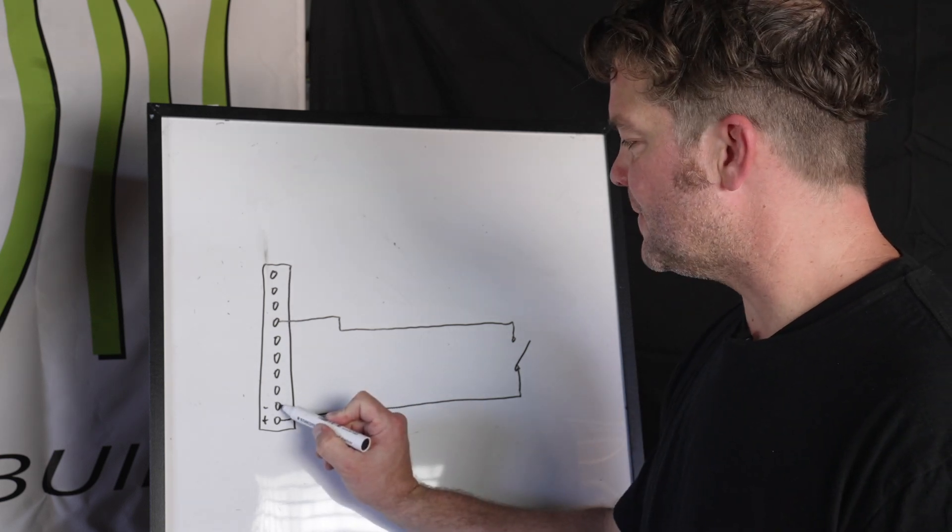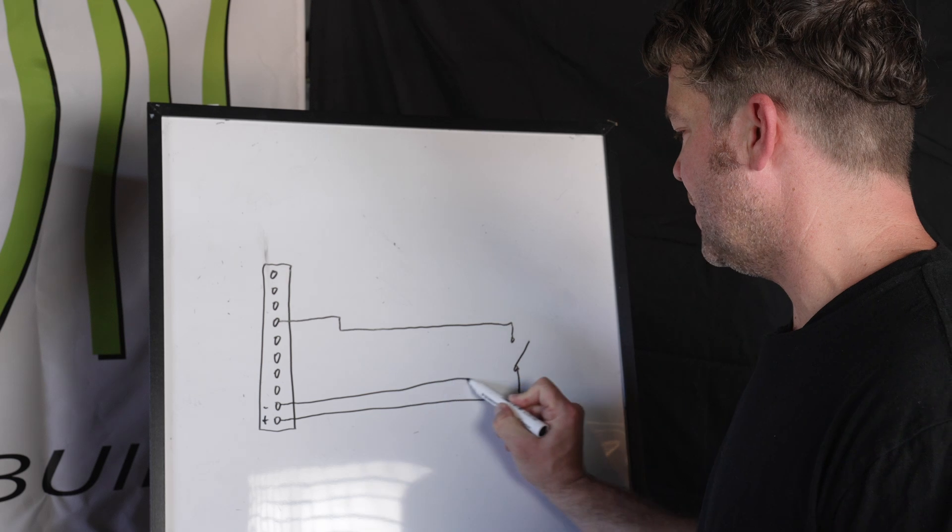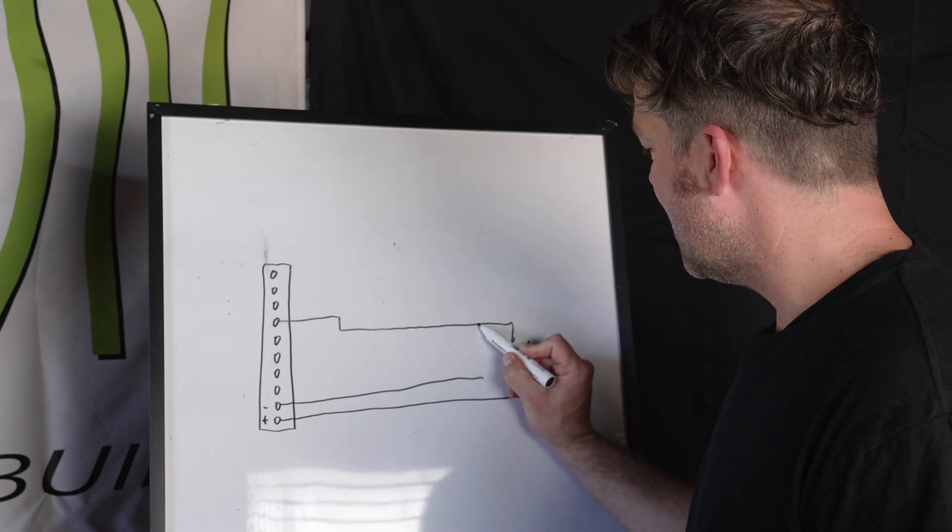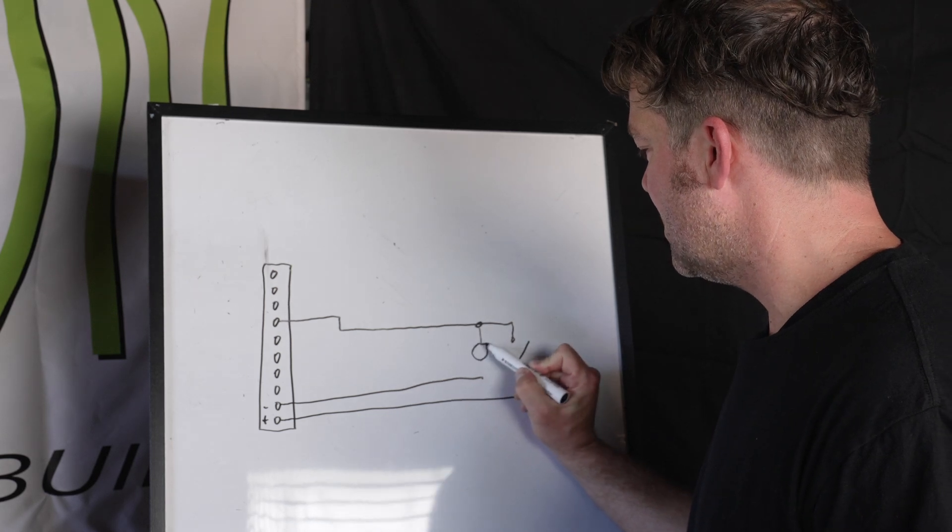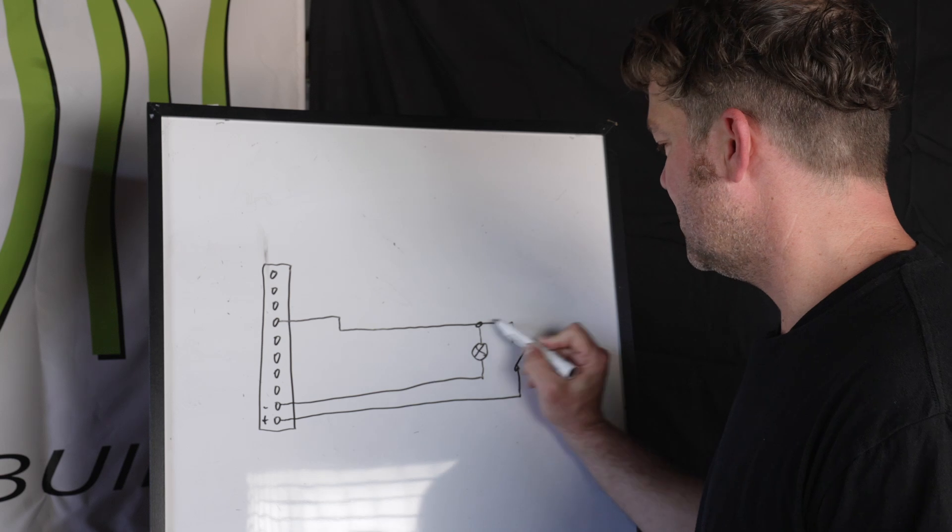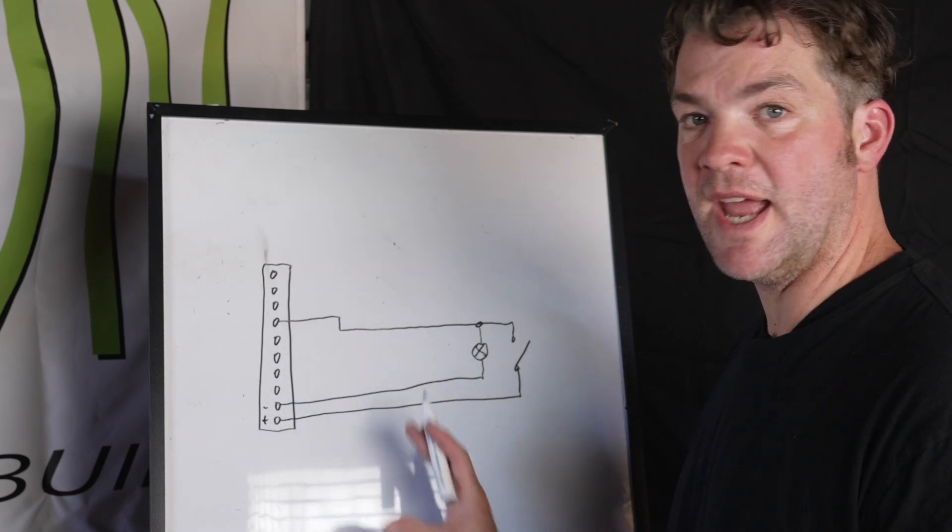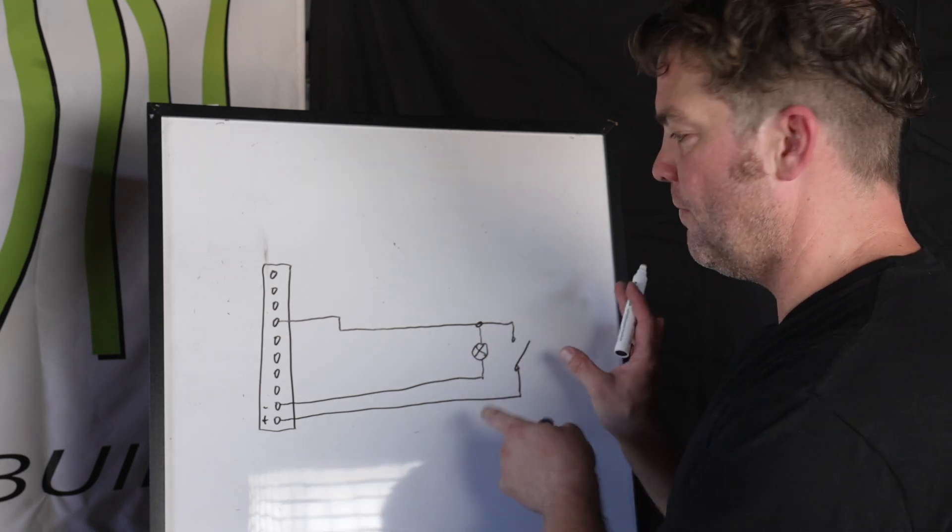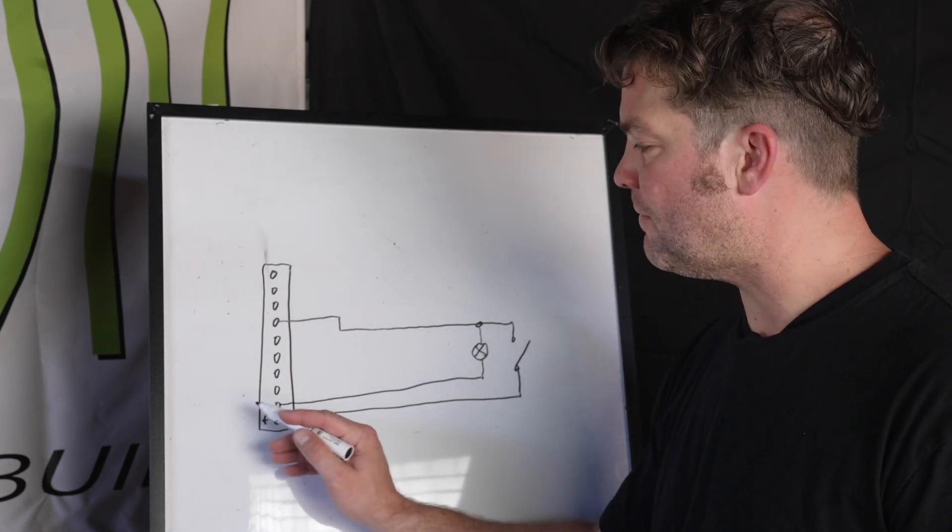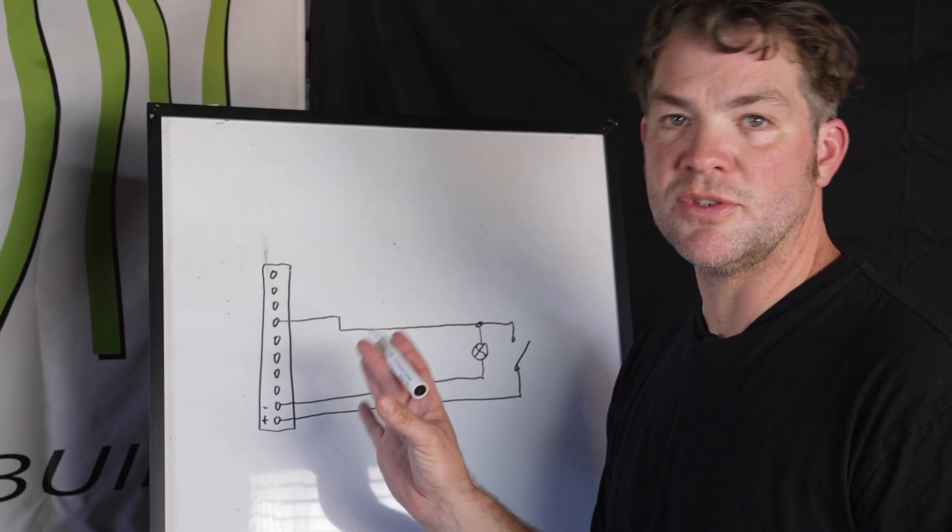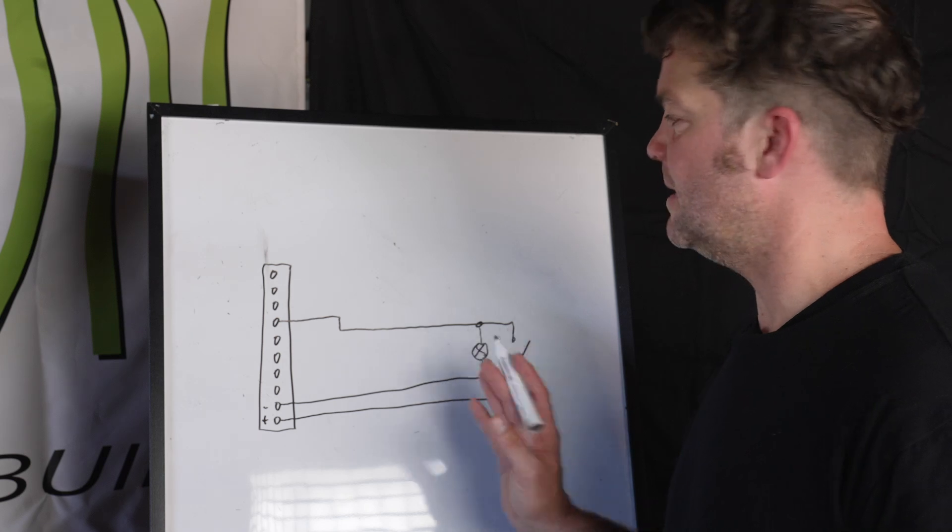The negative is here because most switches have got a control light and that means as soon as you get power onto the output the control light will come on. That's why we got positive and negative especially just for the switch supply. A three amp fuse is enough for this because the relays usually use around 250 milliamps to activate. So it's plenty.